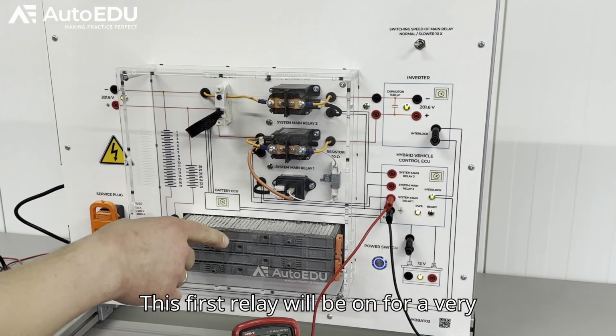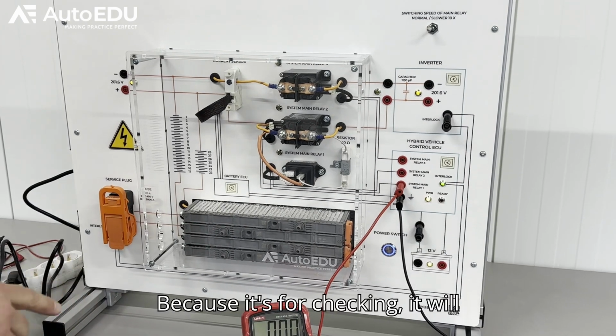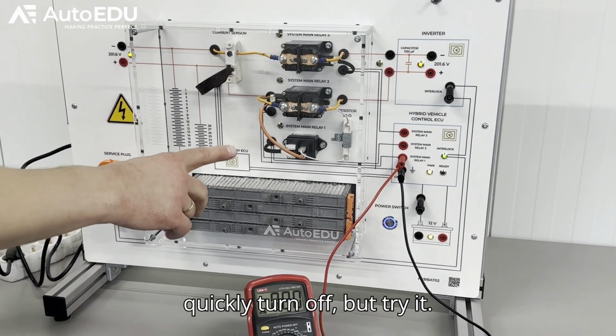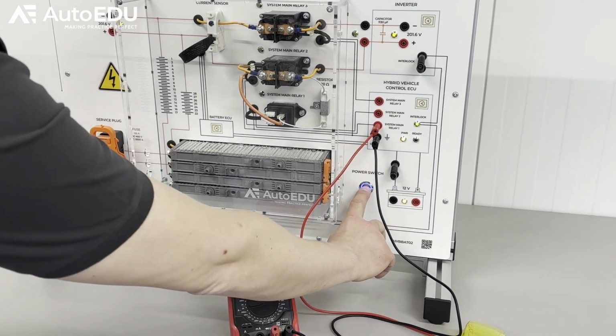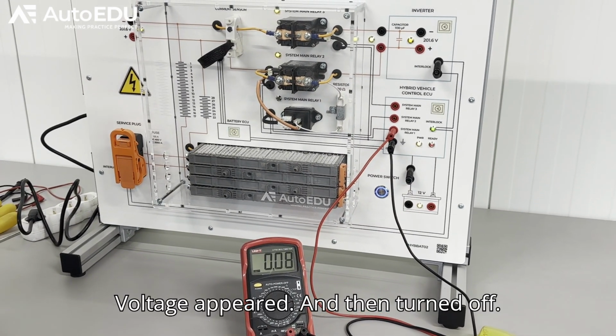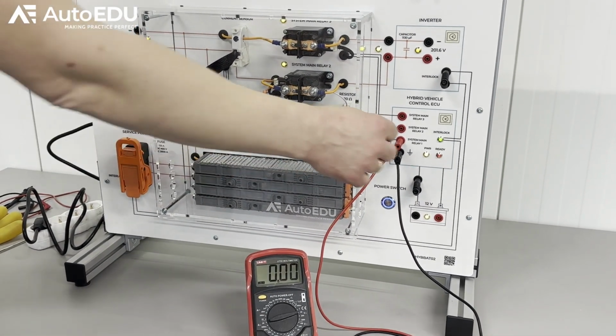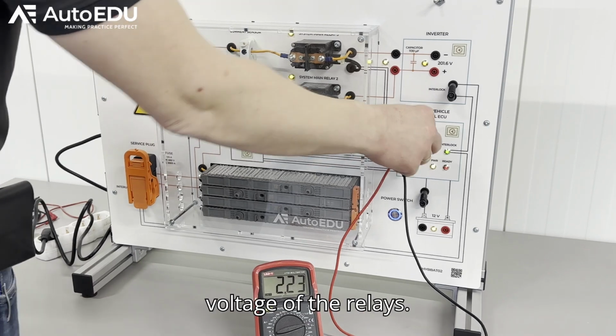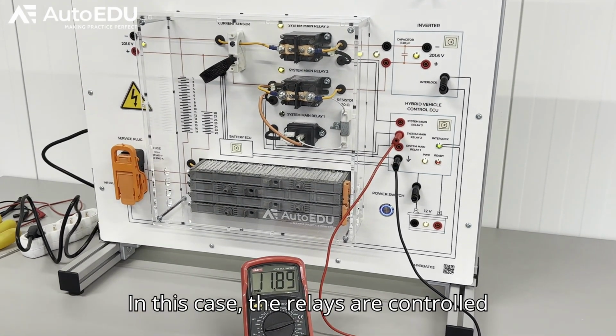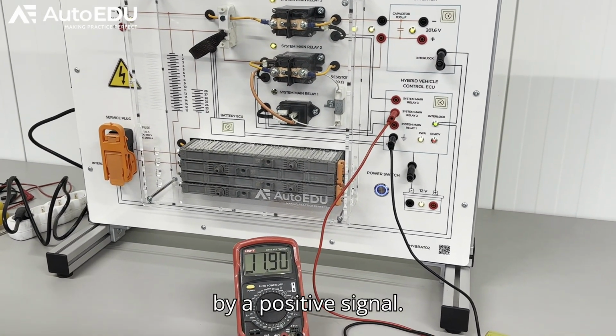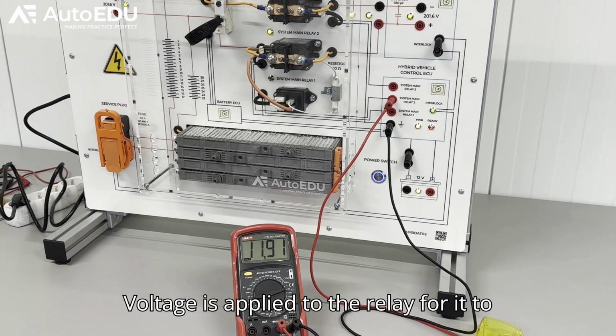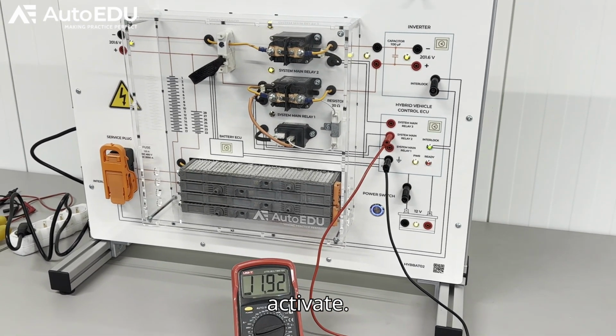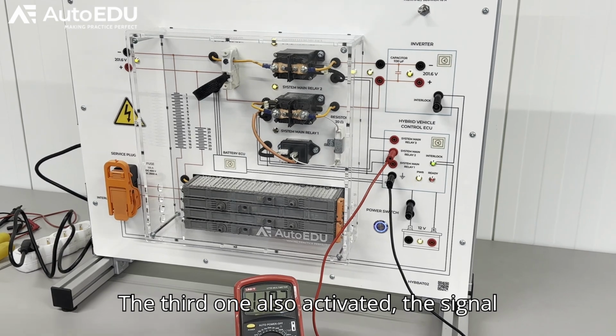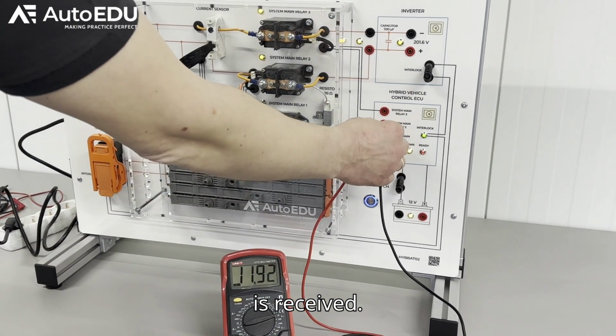This first relay will be on for a very short time. Because it's for checking, it will quickly turn off. But try it. Voltage appeared and then turned off. We're actually measuring the control voltage of the relays. In this case, the relays are controlled by a positive signal. Voltage is applied to the relay for it to activate. The third one also activated, the signal is received.